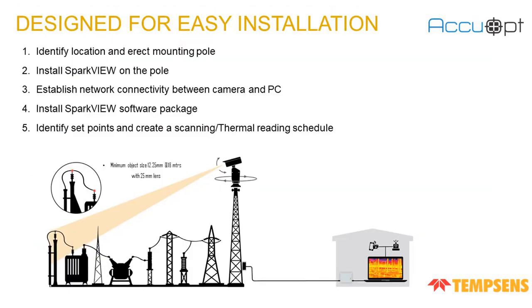This is the installation design for erection of the SparkView system. The SparkView system will be installed at a height of 2 to 3 meters above the highest equipment so that it can have a clear view of the components and the camera will have a clear line of sight to measure the correct temperature. We will identify the location, erect the mounting pole, install the SparkView on the pole, and establish network connectivity between the camera and the PC from the field to the control room. We then install the SparkView software package at the control room, identify set points, and create a scanning and thermal reading schedule.